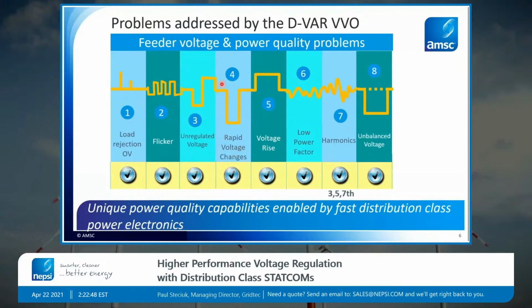Rapid voltage changes are commonly caused by motor starting events. Big, large inrush, we did a tech talk on that. STATCOM's fast enough to compensate for that. Voltage rise: because it can go inductive, it can pull down voltage rise, especially due to DG. When you have a lightly loaded feeder with a lot of DG, it's all about bringing the voltage down, and STATCOM's ideal for that. And then a couple more: STATCOM can filter harmonics actively. So STATCOM is not a dedicated active harmonic filter. However, when it's installed on a feeder, it can additionally be used to filter the 3rd, 5th, and 7th harmonics. And then lastly, unbalanced voltage.